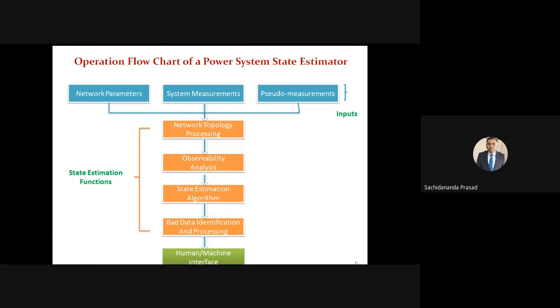Then the most important task performed by the estimator is called bad data identification and processing. Sometimes while sending information from the grid to the control center, there is a chance we may send bad information. For example, suppose 5 ampere or 100 ampere current is flowing in a line, but due to mistake or communication failure, though I reported 100, somebody recorded 200 at the control center. That is called bad information, a huge error at the input end, so that is called bad measurement.